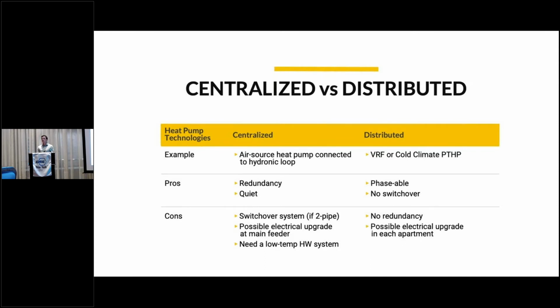The first being you actually have to have a hydronic network to capitalize on a centralized system. You do have to still do a seasonal switchover if you're injecting at a central location, because you're either operating your heat pump in a heating or cooling mode. That's only if it's a 2-pipe system. If it's a 4-pipe system, you're good, but not too many buildings have 4-pipe systems. And then the other thing that you have to consider is that a lot of buildings in New York City are a little older, and so they might not have the electrical capacity to handle a large centralized heat pump installation.